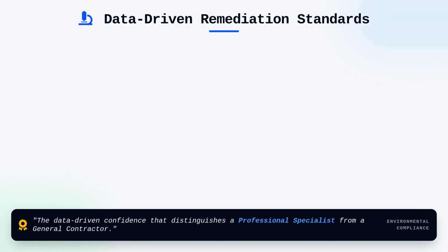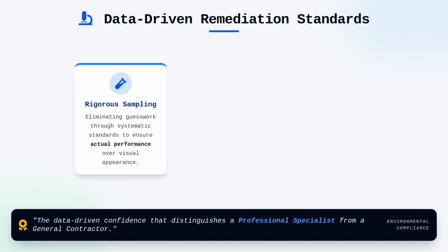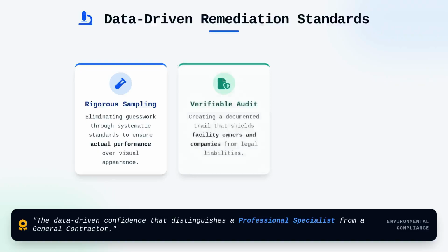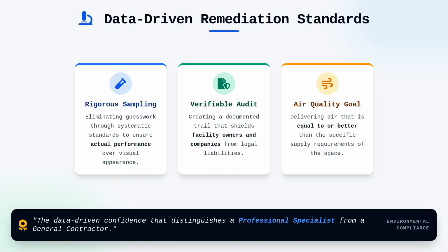specifications and environmental guidelines. By adhering to these rigorous sampling standards, you ensure that the air system does not merely look clean, but actually performs its function of delivering healthy, filtered air. This systematic approach eliminates guesswork and creates a verifiable audit trail that protects both the facility owner and your own company from potential liabilities. Always keep in mind that the goal of testing is to ensure that the air being delivered by the system is of better or equal quality to the supply air requirements of the space.